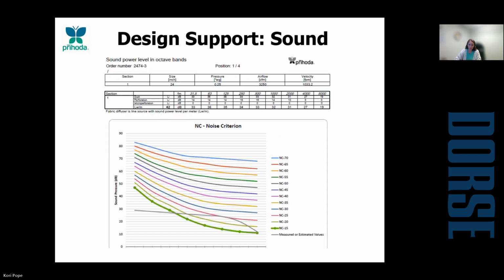So Airtailor also gives us the ability to generate the sound data across 9 octave bands so that we can then plot that to determine NC levels for the duct diffusers. So one thing to note is that our product is fabric. So while it in itself is not going to generate any type of noise, our ductwork can carry noise from upstream of us. So if you are in any sound sensitive applications, we always highly recommend to have some sort of sound attenuator upstream of our ductwork.